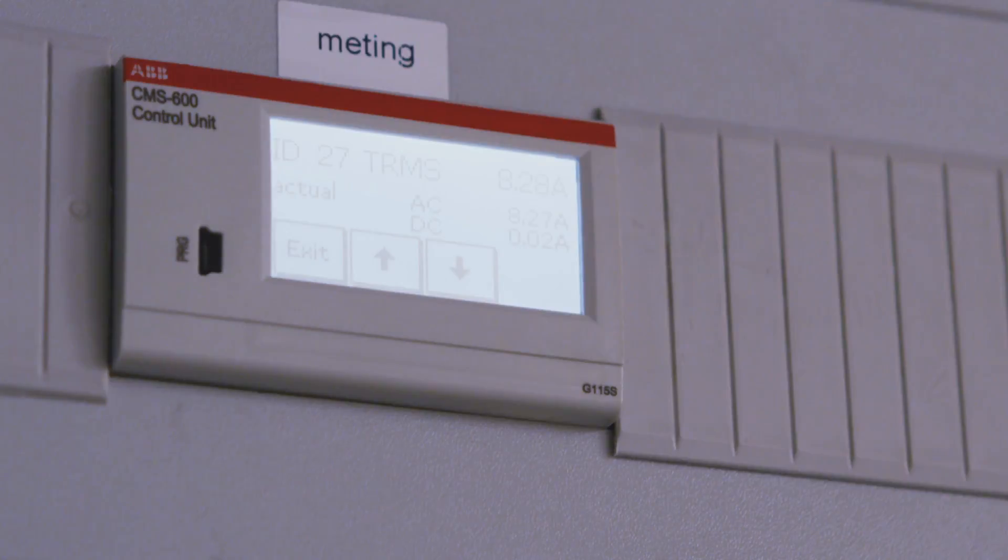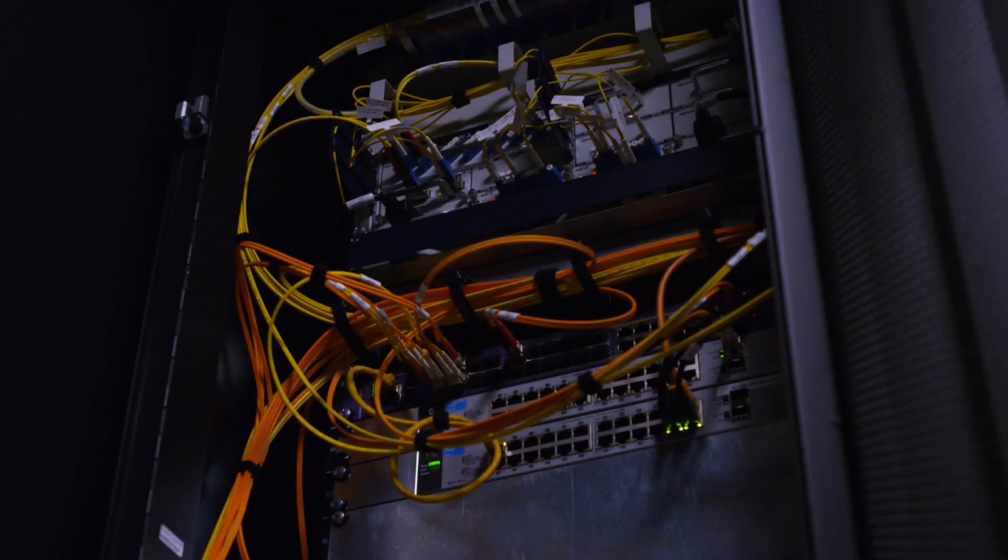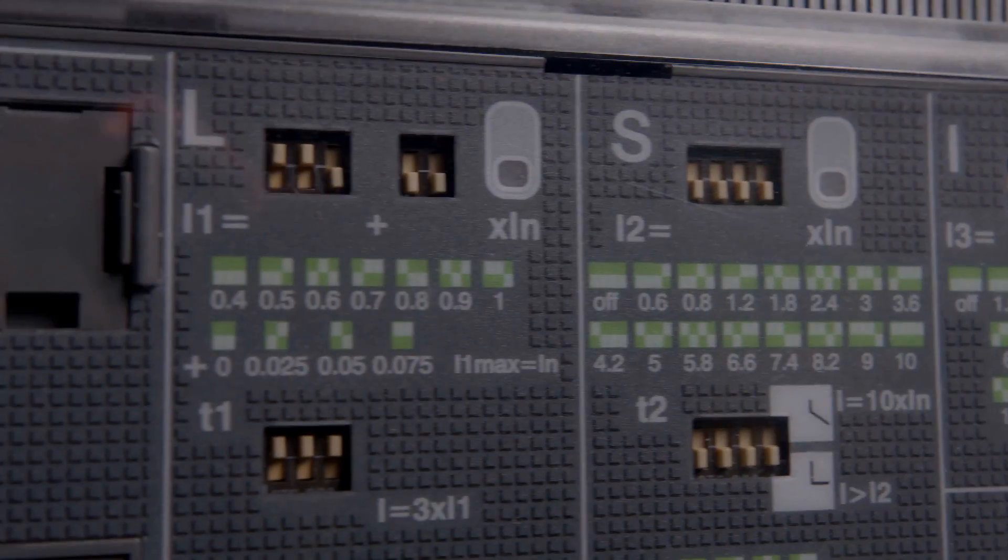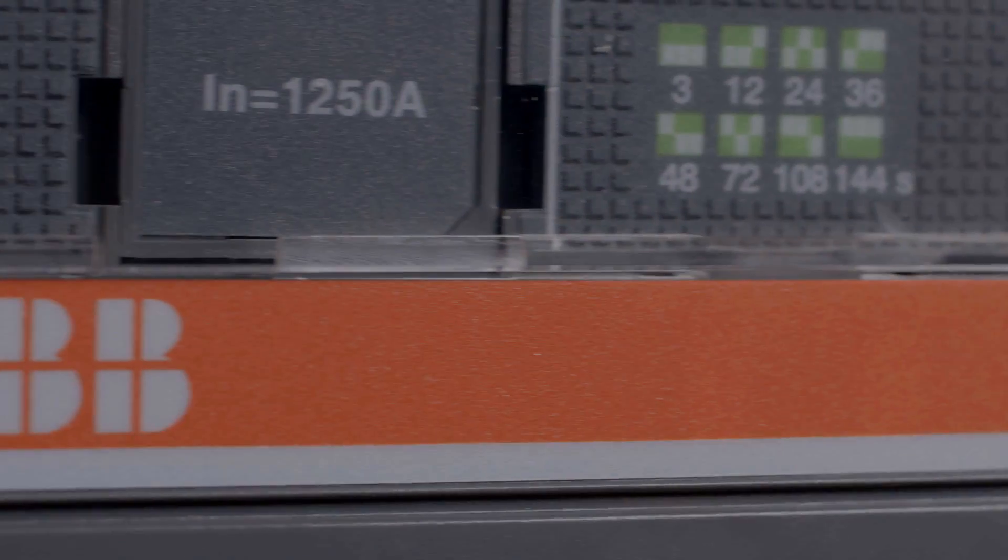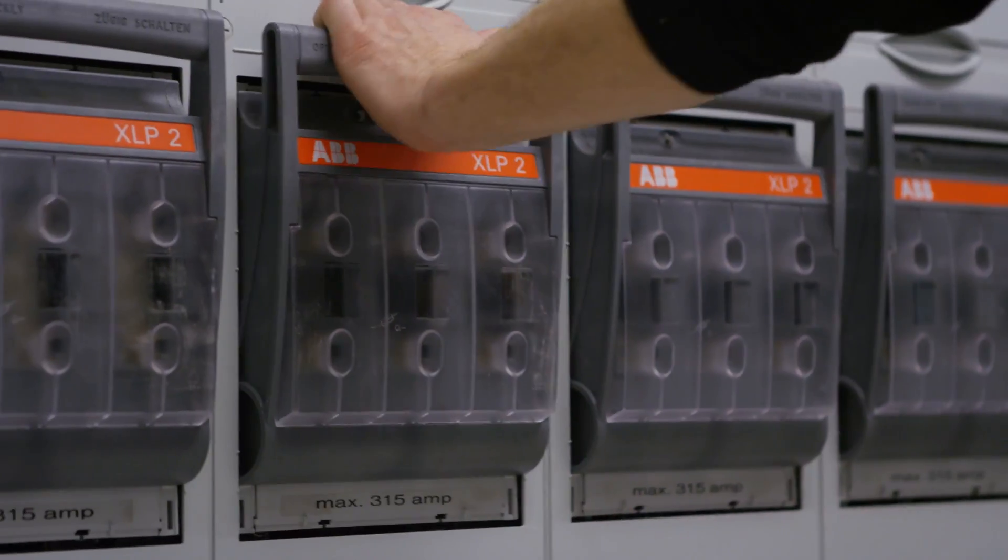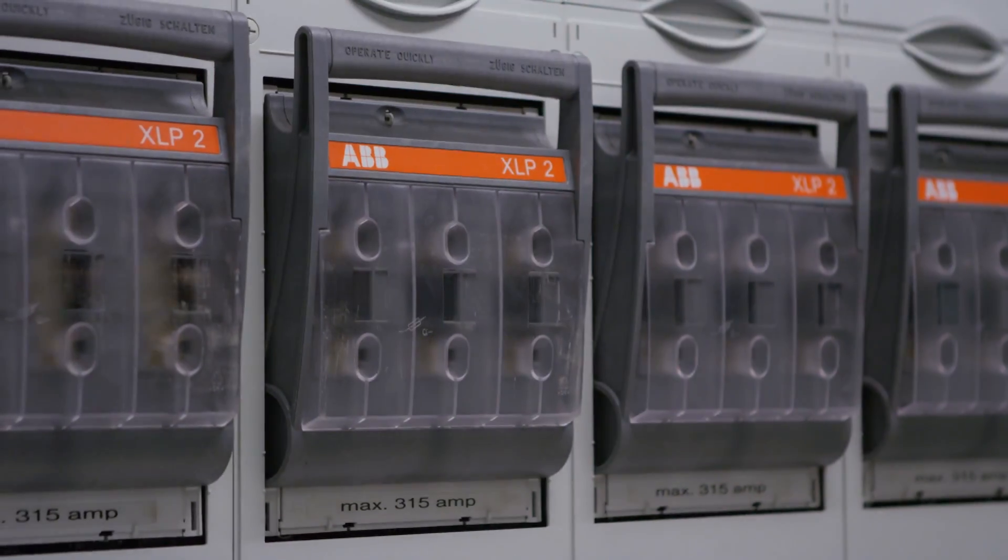What we saw in the past, if there was a failure in the data center, nearly 100% of the failures was because of one of the circuit breakers failed. So we looked into the specs of the circuit breakers, especially for server systems.